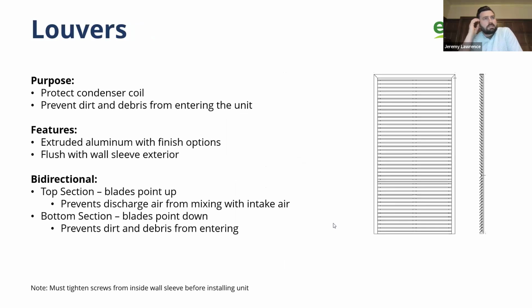No. Inspectors are not. It's because the ERV itself has its own integral fan, and it's pushing out into the sleeve, but then the condenser fan is pushing out as well. It's so diluted because of the size of this grill, that it's actually going out is 20 by 46, I think, something like that. No, inspectors have it's all been approved, and it's up. These units are all approved to the new CO2 standards and fresh air standards with ASHRAE.